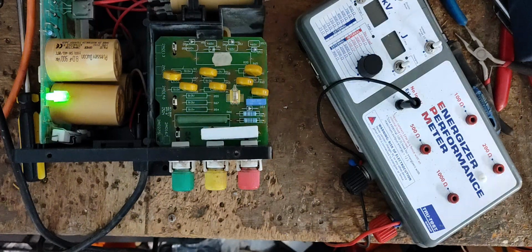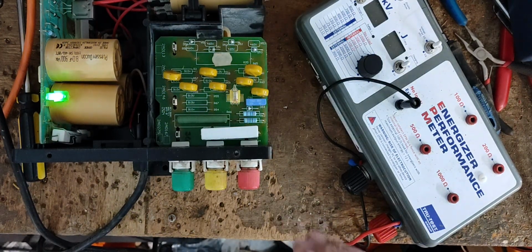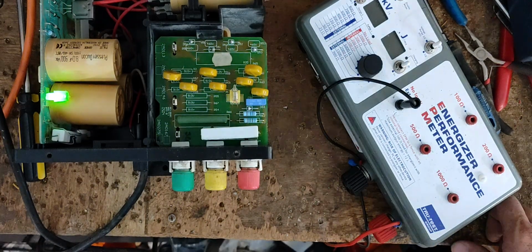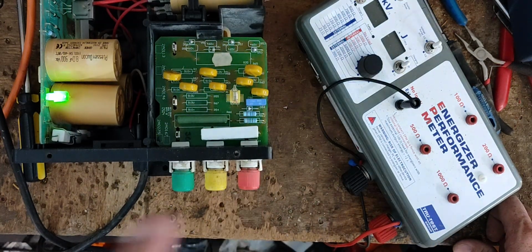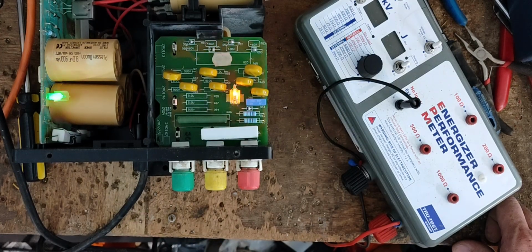You can do this in the field as well. All you've got to do is have the ground system hooked up only, and plug it in with no fence, just a ground system, and do the same thing. If it keeps on flashing and clicking, the transformer's fine. If it keeps clicking but the light goes out, you've got an internal short in the transformer.